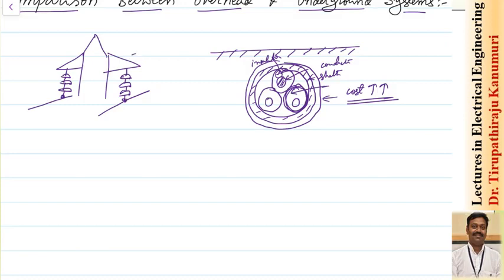In the case of overhead transmission lines, the advantage is that conductors will be hanging from the tower — the cost will be the cost of the tower and the cost of the insulation. Practically it is observed that the cost of the overhead transmission line including all costs will be only 50% of the underground system.